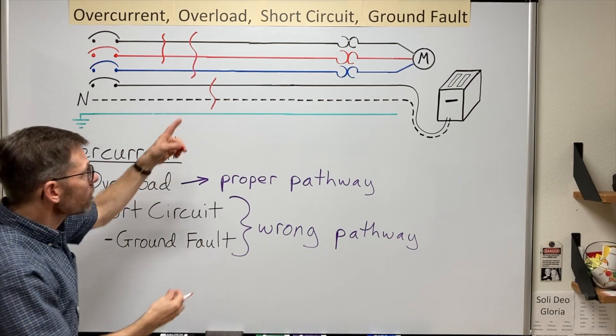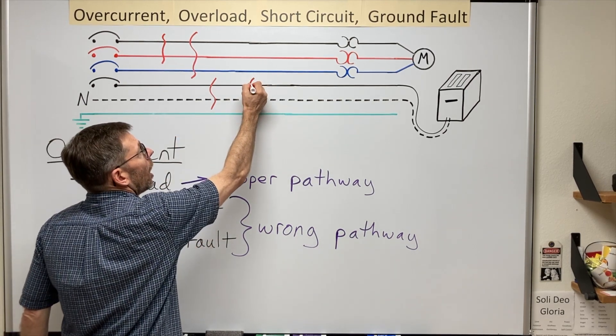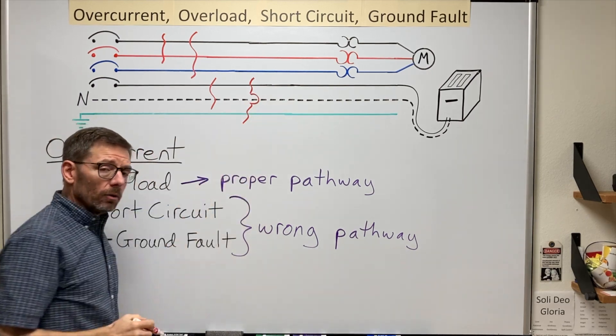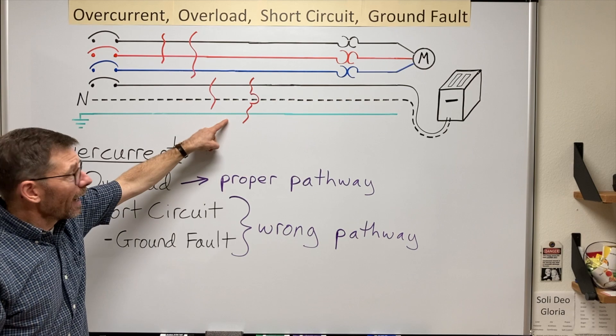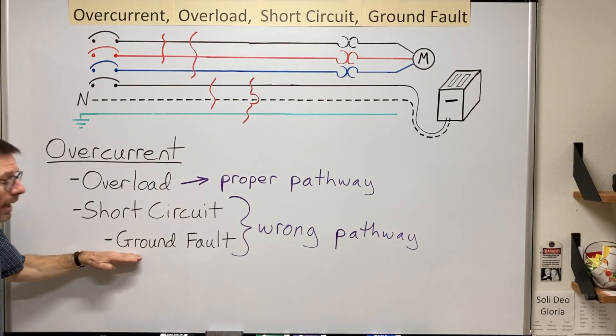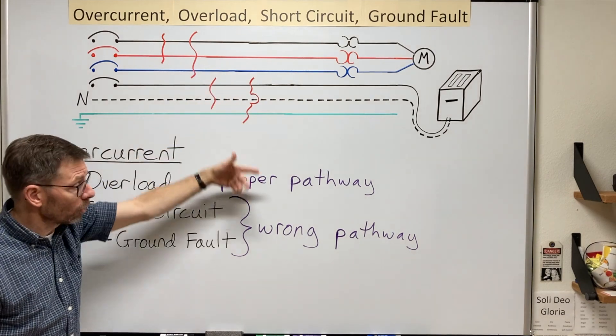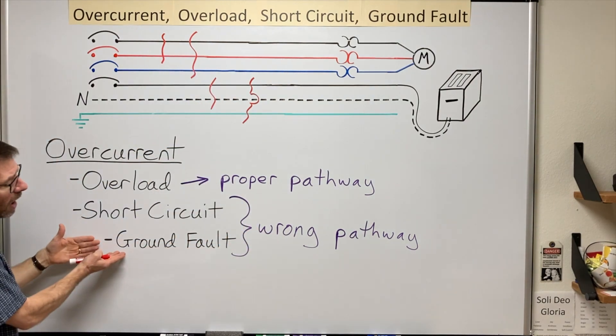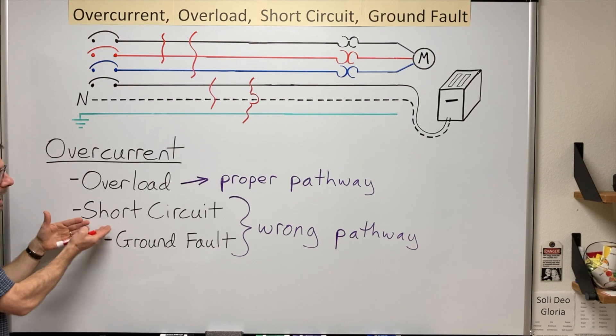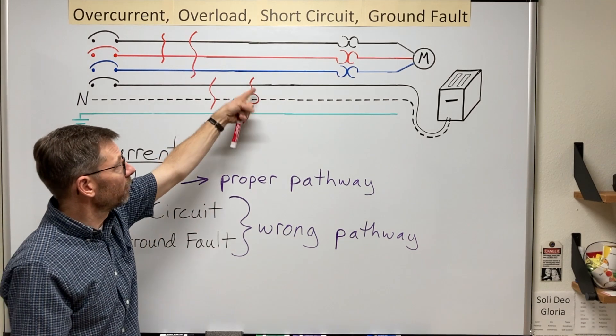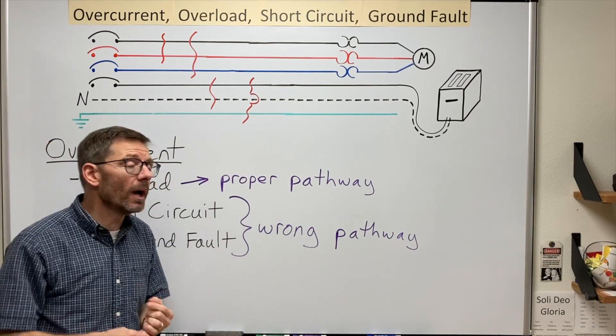Now, we could also have a hot to the ground. Now, whenever the ground is involved, we call it a ground fault. So it's still a short circuit, still taking the wrong pathway. So you'll often see ground fault as a subcategory of short circuit. And a lot of current can flow there as well. We want that device to open right away.